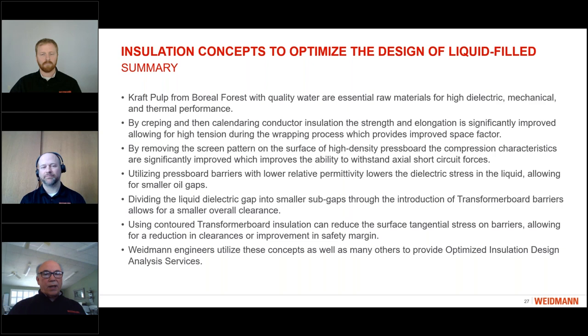Space factor, I'm not sure I defined that earlier, but when you're looking at designing a transformer winding, ideally you want to put as much copper into the winding space as you can, or conversely, knowing how much copper you need to carry the current, you can make the winding smaller by having a better space factor. So if you imagine doing that on the inner winding, that's going to then be even more amplified on the outer winding. So you can make some significant improvements in the overall size of the transformer by using this calendared creped conductor insulation.